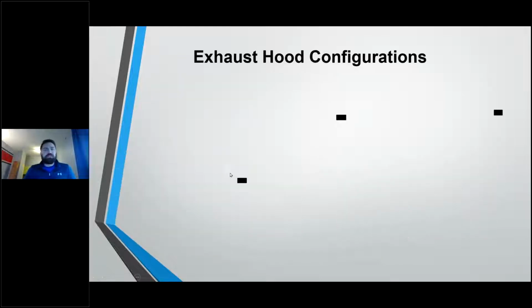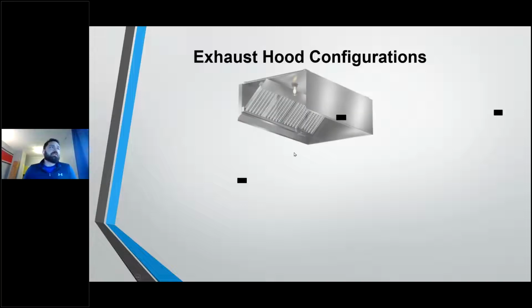Next, we're going to jump into the different exhaust hood configurations that we have. So first and foremost, the standard wall canopy exhaust hood is going to be your standard configuration. So this will be a canopy hood, typically 24 inches or 30 inches tall, mounted along a wall with baffle filters, with some sort of grease filtration, lighting, and again, a 24 or 30 inch top.